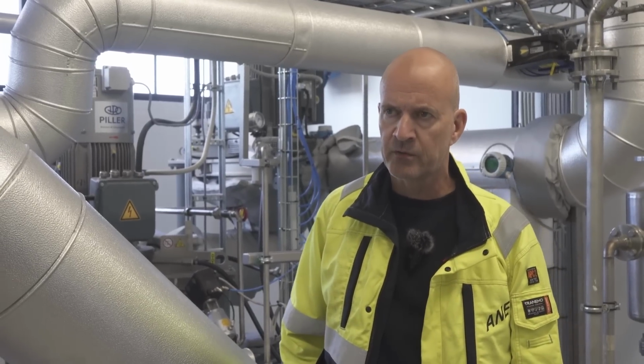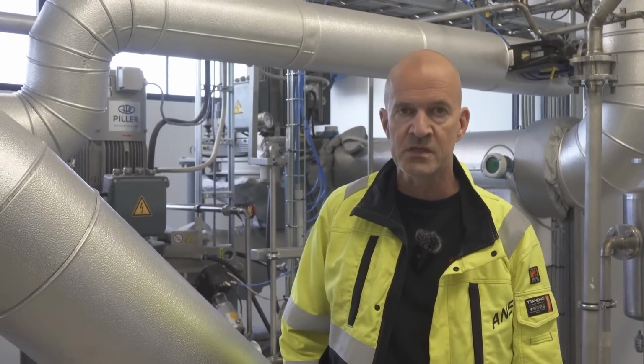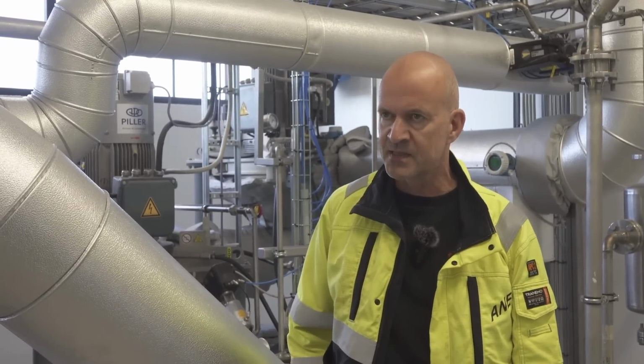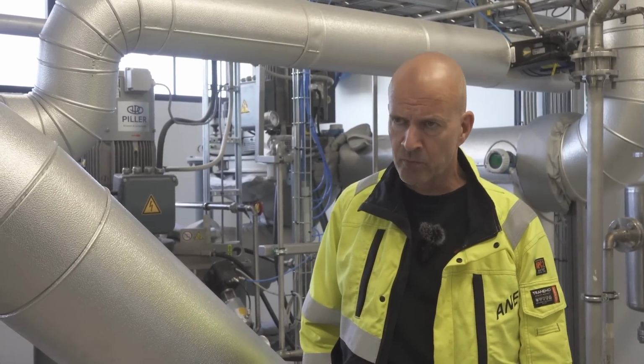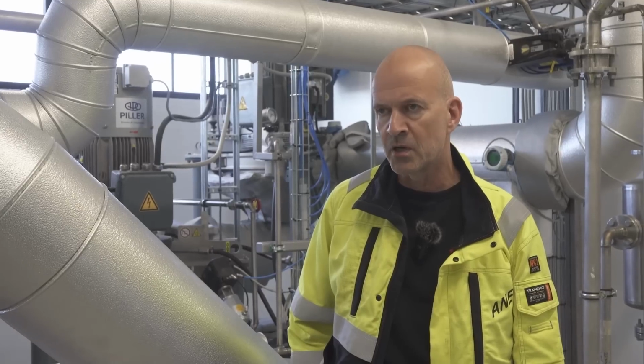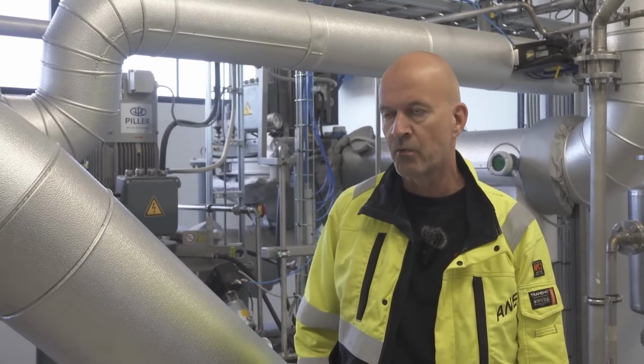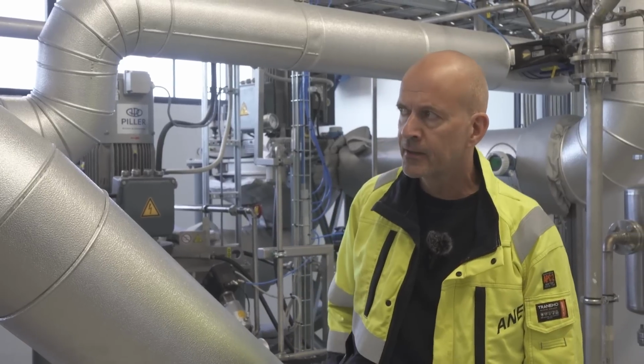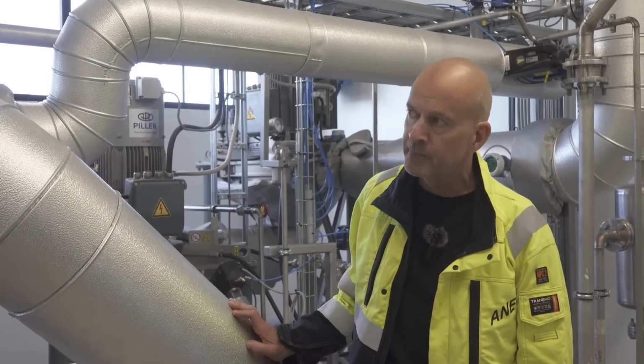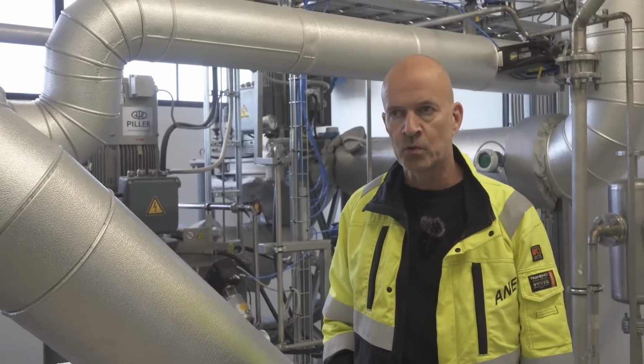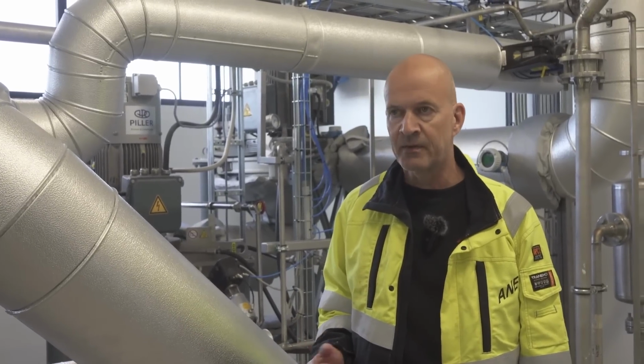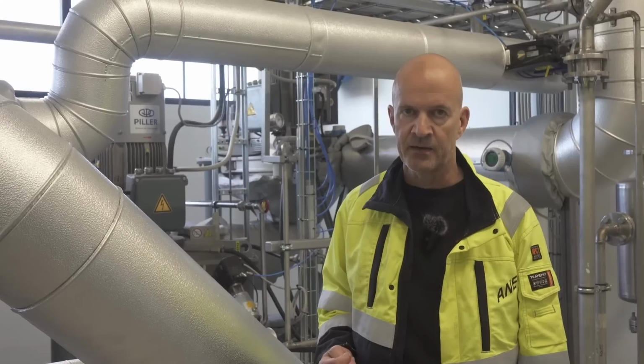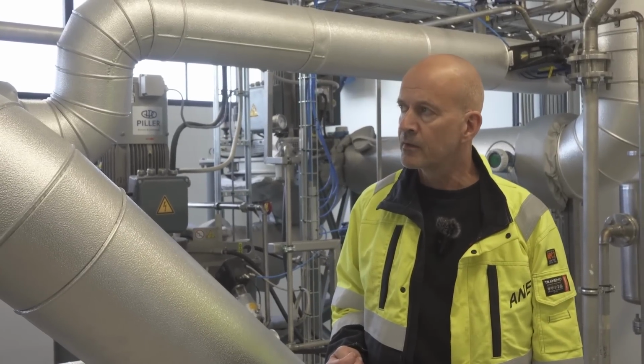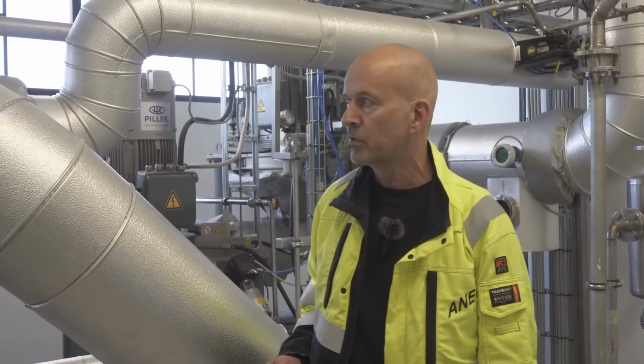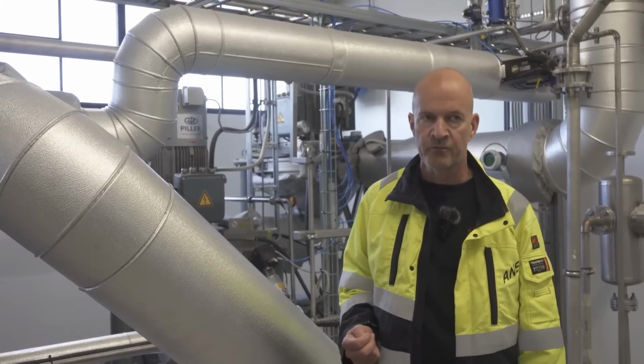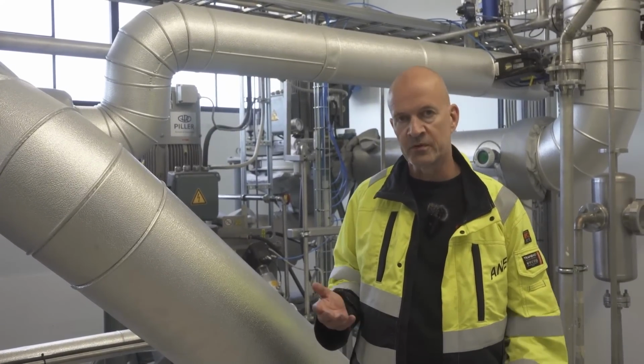This setup here at Felleskjøpet uses about 1.2 megawatts of excess heat, and at maximum peak we produce about 2 tons of steam per hour. Regarding efficiency, the COP ranges from 3.1 to 3.4 depending on operational conditions in the factory. This setup also accommodates a temperature lift from about 90 to 100 degrees.